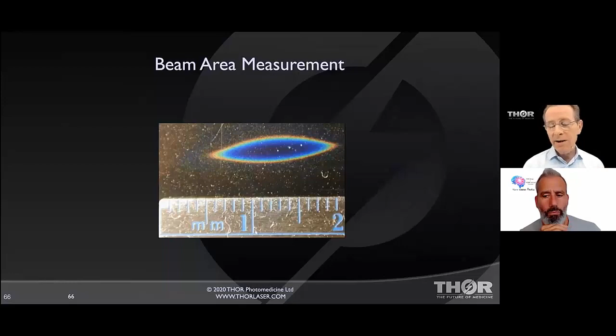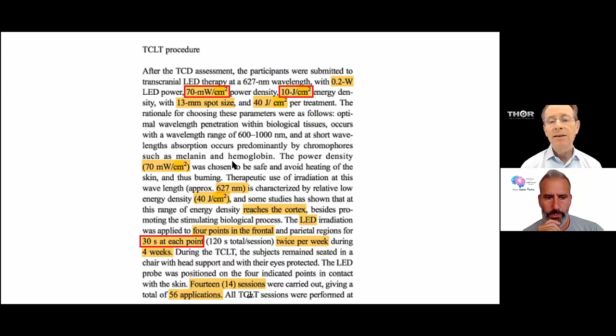Paolo Casano sent me this, said, James, can you check this for me? It doesn't make sense to us. We think there's something wrong. Could you have a look? And I did. And sure enough, 70 milliwatts per centimeter squared, it says up there, was with treatment for 30 seconds, was reported as 10 joules per centimeter squared there. And yet I calculated, and you can see at the top there, it was actually 2.1.